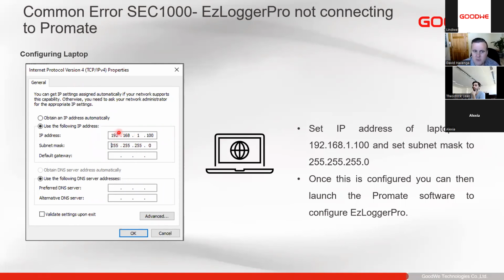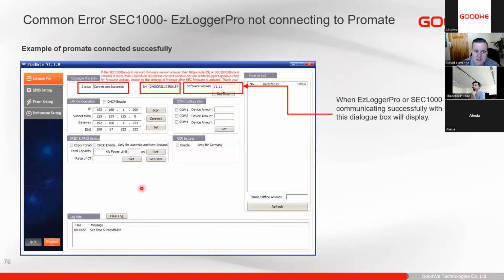So it's 192.168.1. The easy way of knowing what to do is in the next slide. In ProMate, you'll find the default IP address of the logger. When you open ProMate, this is already there. So all you do is make your IP address the same first three numbers, and then the last number just different. It can be 201, it can be 1, it can be 100, anything within the range that you can set for an IP address, just not 200, because 200 will be the default IP address of the logger.